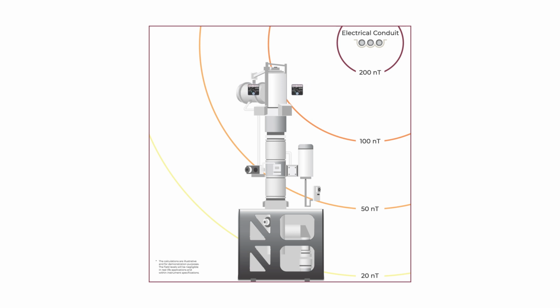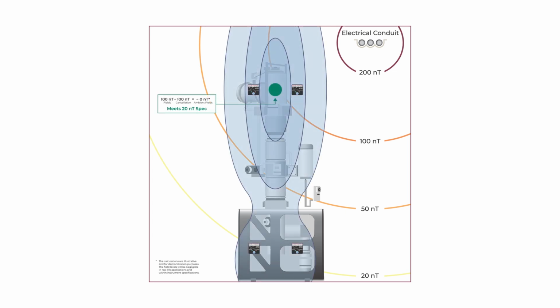So let's talk about how a dual cancellation system plays out in our previous example of an overhead electrical conduit. Because you have two systems, one optimized at the top near the source, one optimized at the bottom near the detectors, the field cancellation system at the top cancels that 100 nanotesla field experienced at the source, resulting in a field level at or near zero. At the same time, the field cancellation system at the bottom is detecting that lower field level of 20 nanotesla and optimizing for the detector location, so the field is at or near zero at the detector. You basically have two optimization points with a smooth transition from top to bottom of the microscope, allowing the entire length of the electron beam column to be within that very tight 20 nanotesla peak to peak specification.